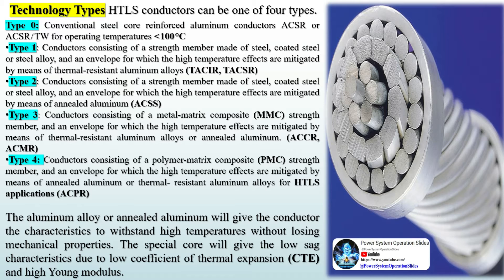Type 4: conductors consisting of a polymer matrix composite (PMC) strength member, and an envelope for which the high-temperature effects are mitigated by means of annealed aluminum or thermal-resistant aluminum alloys for HTLS applications (ACPR). The aluminum alloy or annealed aluminum gives the conductor the characteristics to withstand high temperatures without losing mechanical properties. The special core gives the low-sag characteristics due to a low coefficient of thermal expansion (CTE) and high Young's modulus.